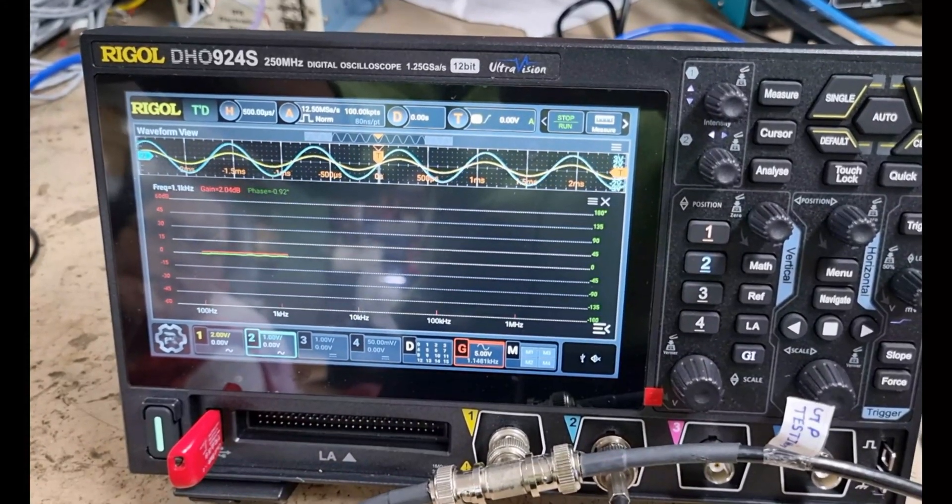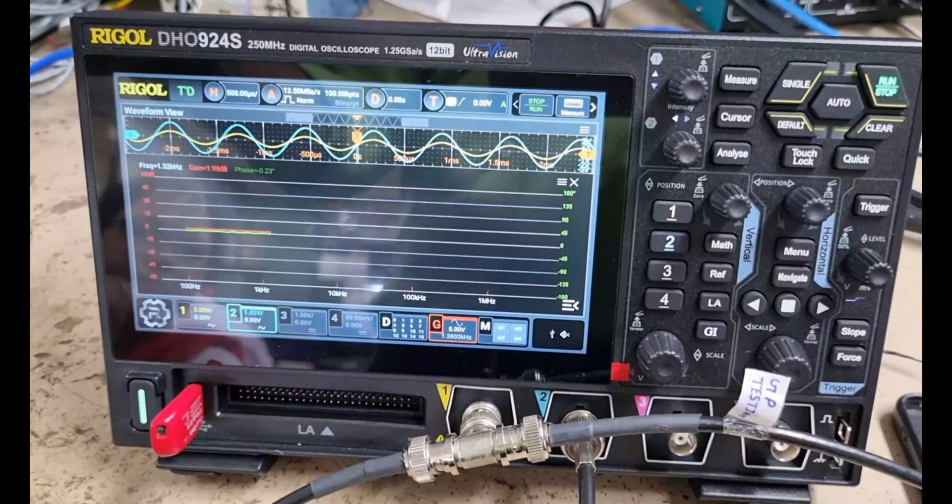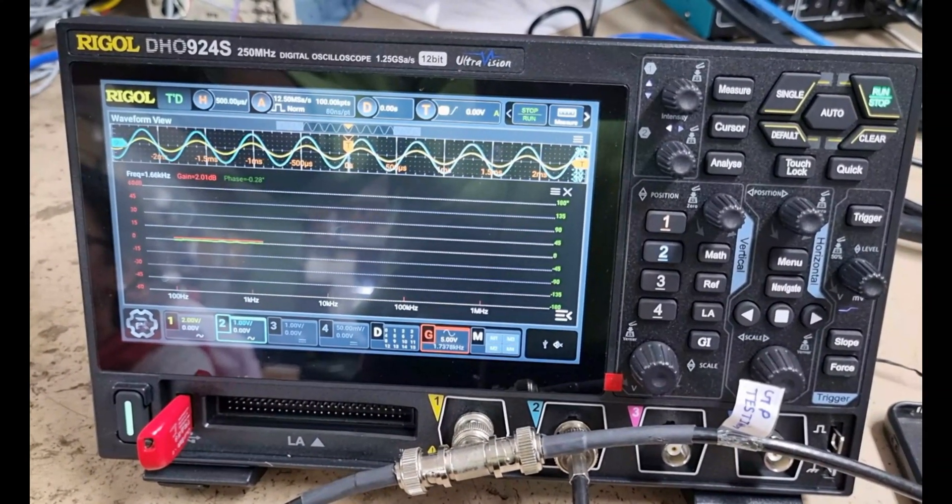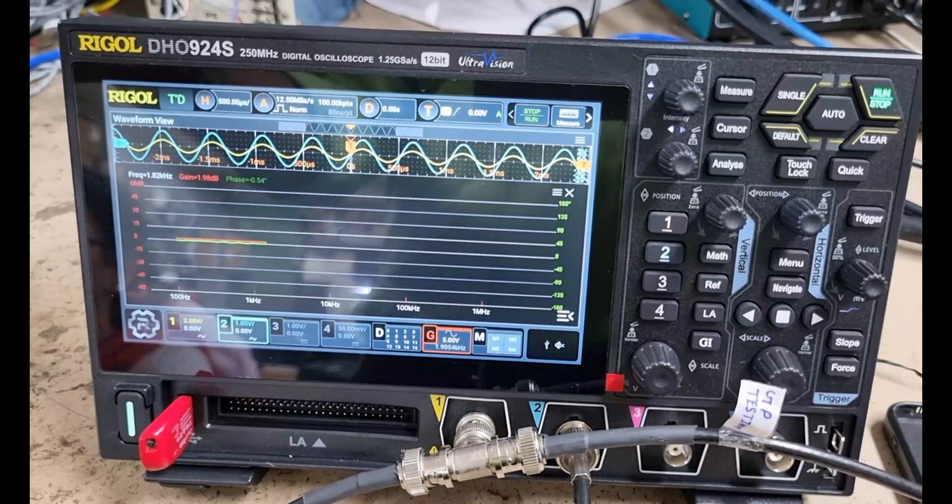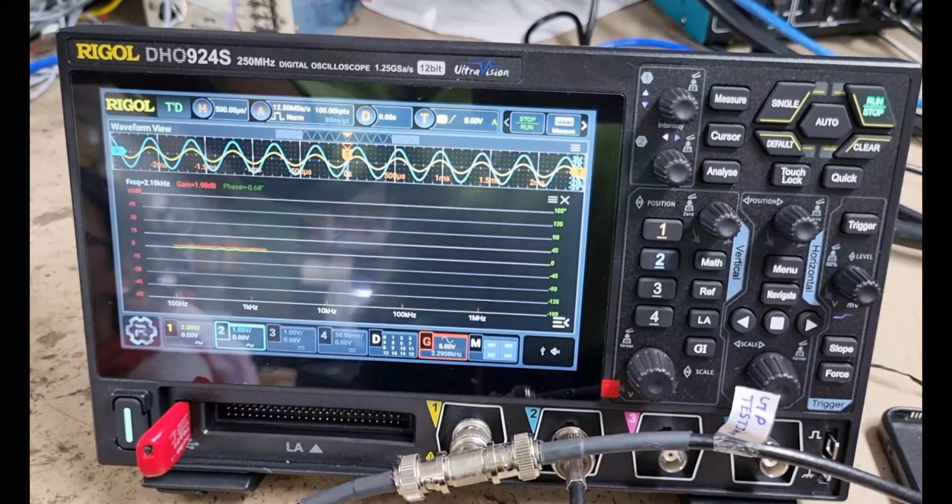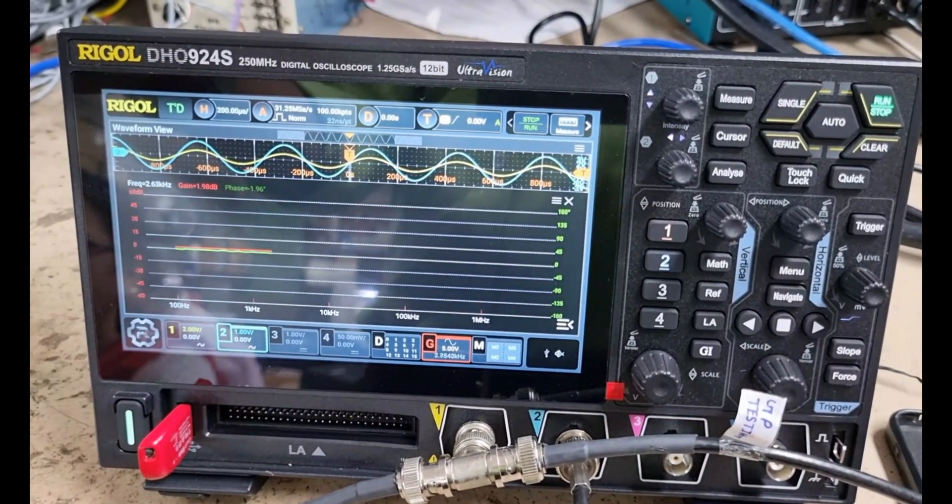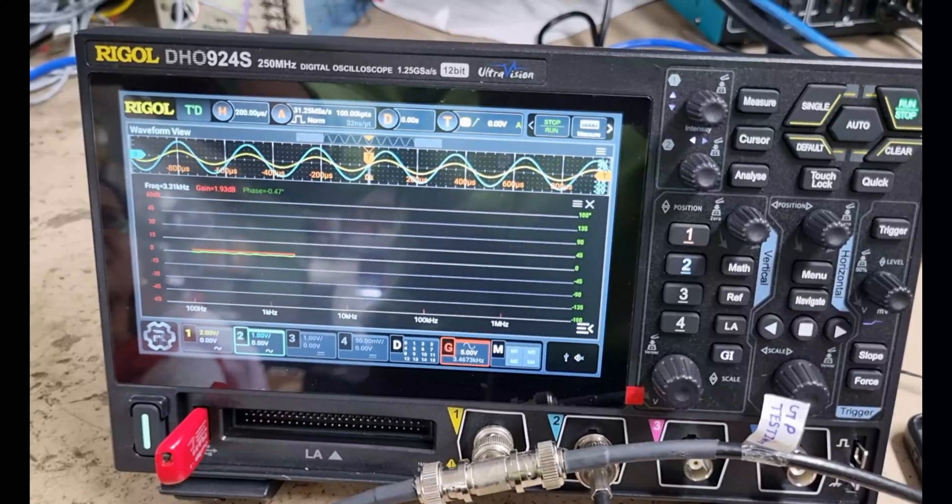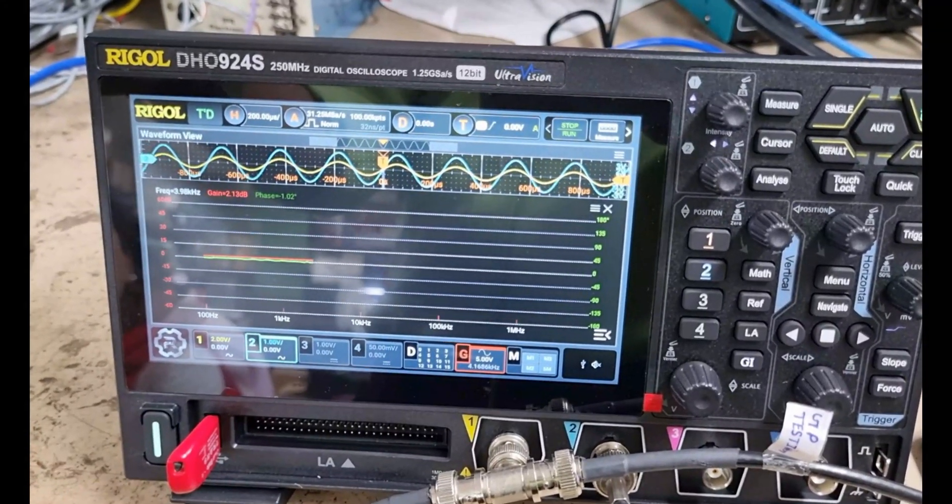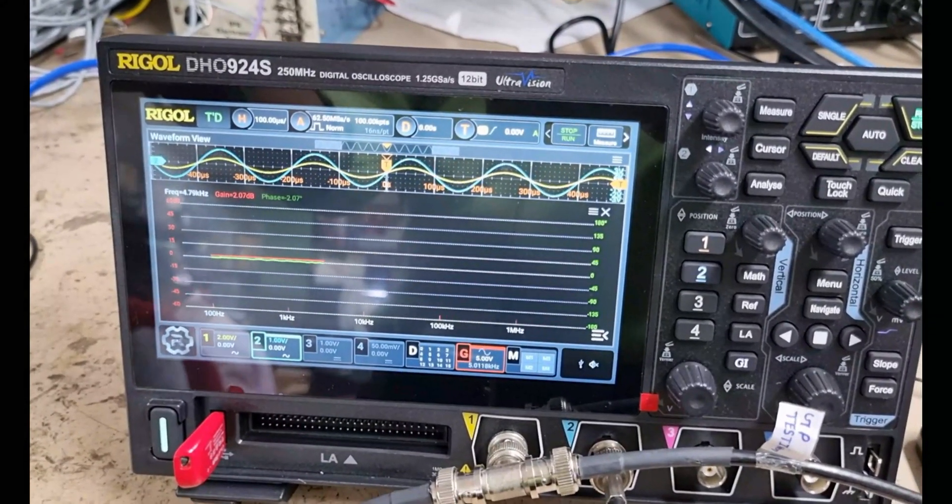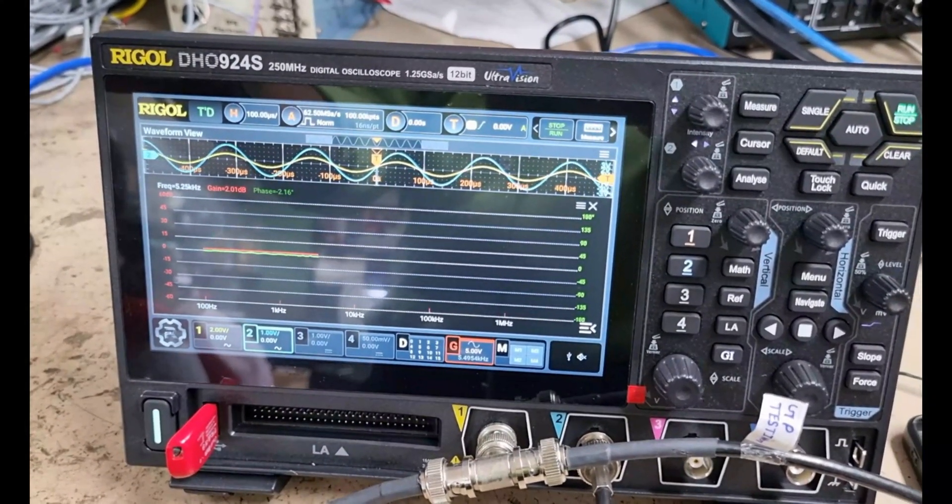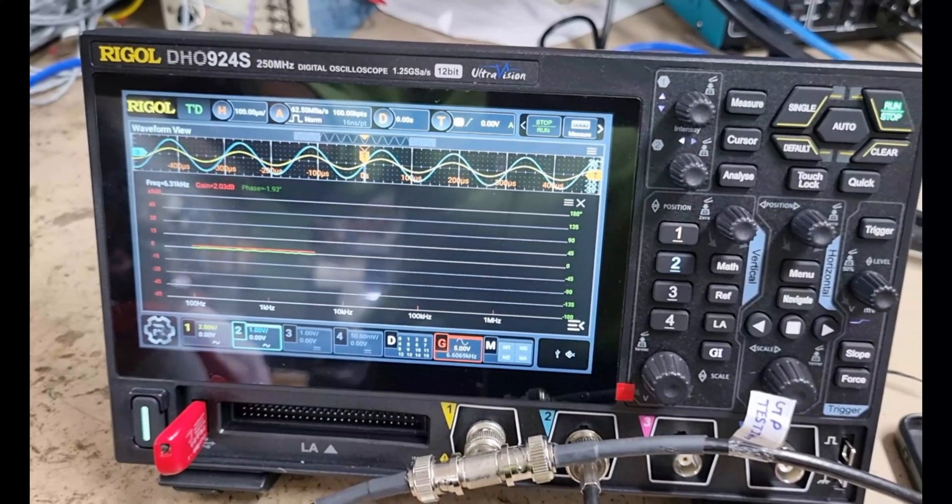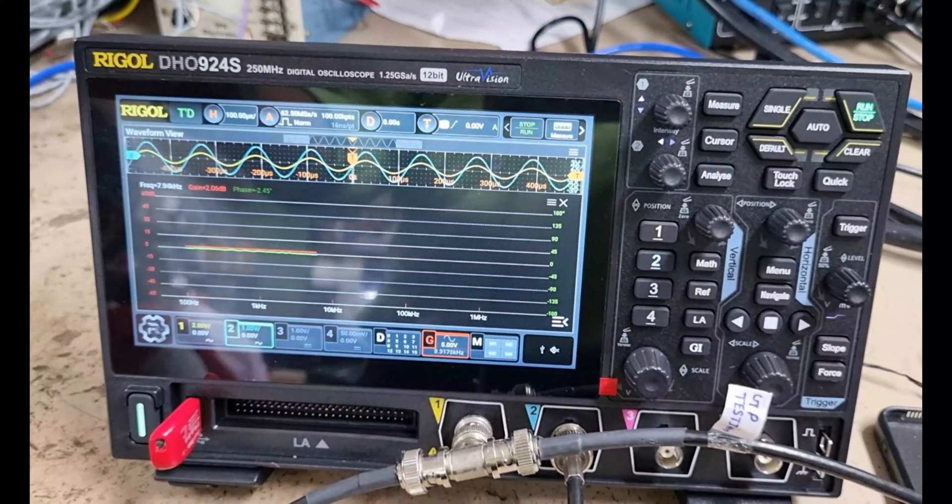In this video, we didn't use a frequency injector transformer because this is a very low voltage application. But if you are working on a high voltage application and performing a Bode plot, you should use a frequency injector transformer to protect your function generator.